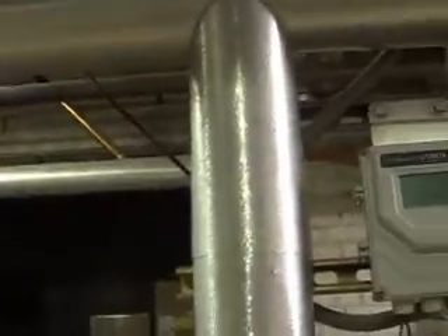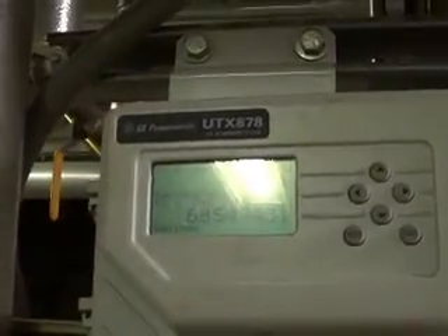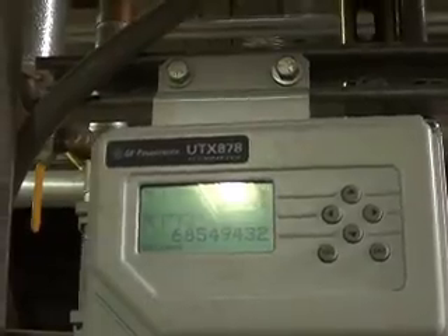I just write it on the back of my hand. That's the one that's operating in lead, and these two are on standby. And I go over here. If we don't have enough condensate coming back, we use that soft water from the city makeup to make up the difference. Here's the valve that controls it. I currently have a little bit of flow going through it, not much.